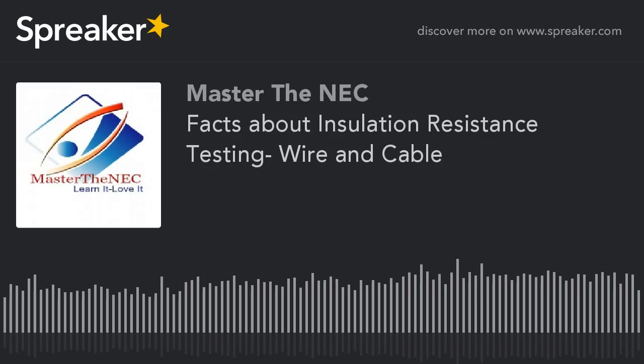However, there are some fallacies in this process. A lot of people today do a lot of testing, and in some cases make quite a good living doing testing. But the reality is that you can't really do the tests that you think you can do with a megohm meter. All you have to do is ask the manufacturers, Fluke, Megger, Hioki, all those, and the engineers will tell you they weren't really designed to test insulated conductor to insulated conductor, and that's typically what we do in the industry. So we're going to talk about those different things and dispel some of those myths.